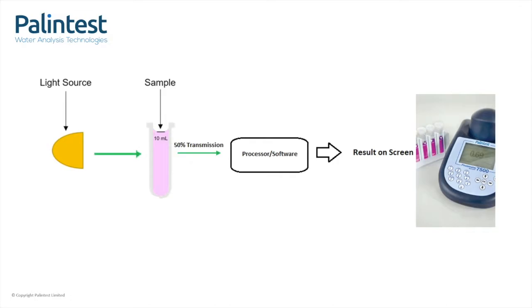So all you need in order to check that the photometer is working is something that you can place in the sample holder for which you already know how much light passes through.